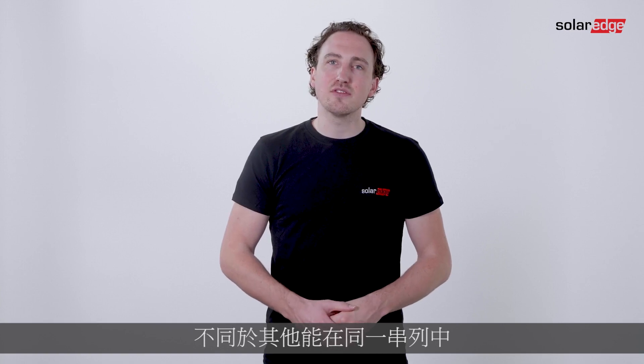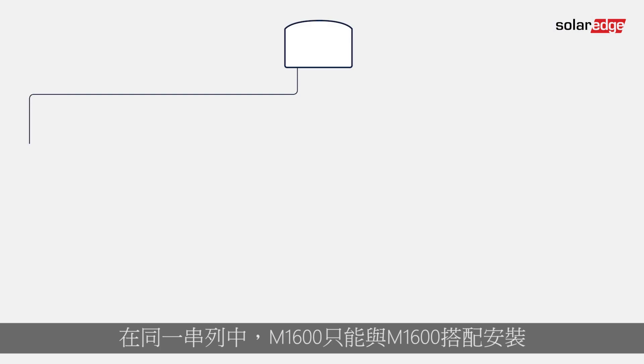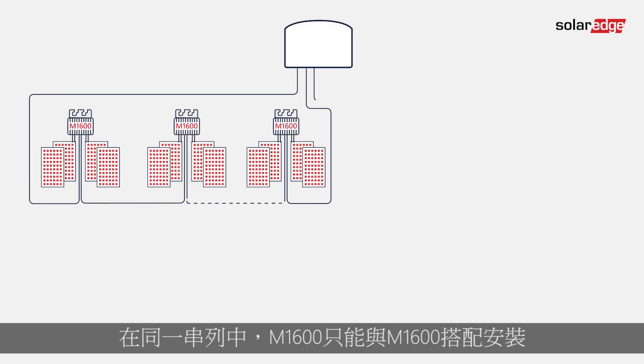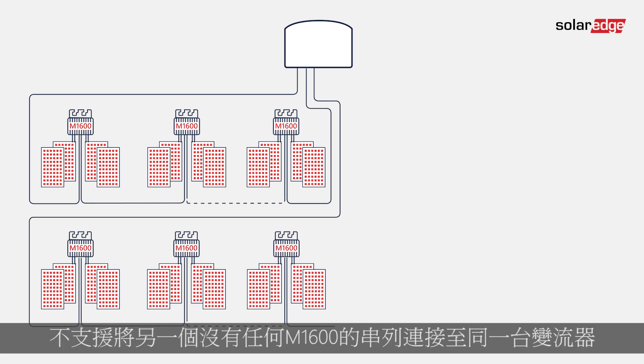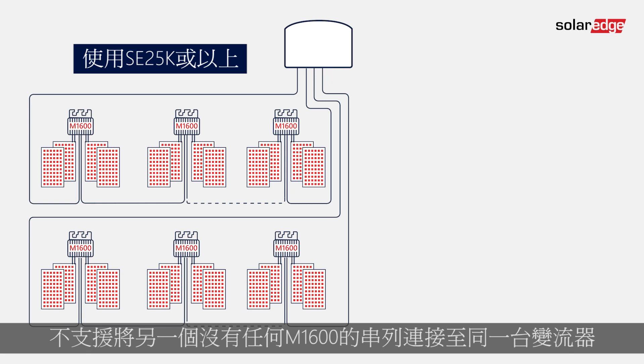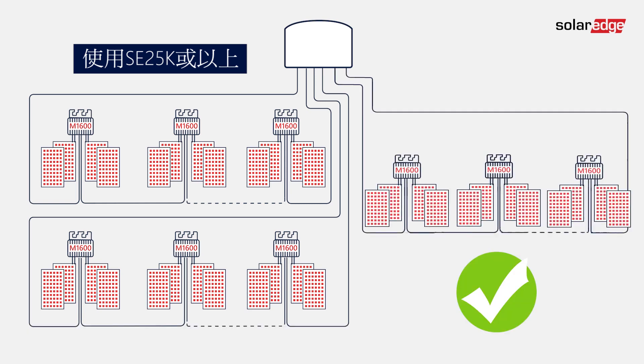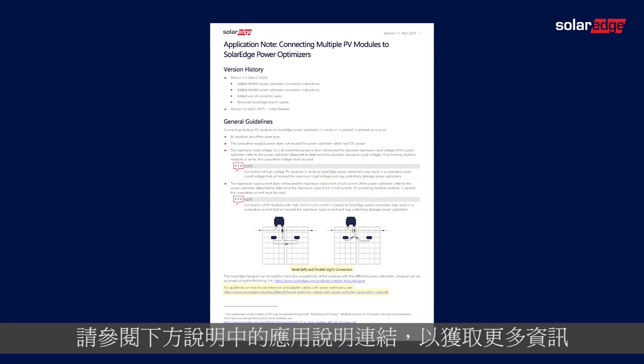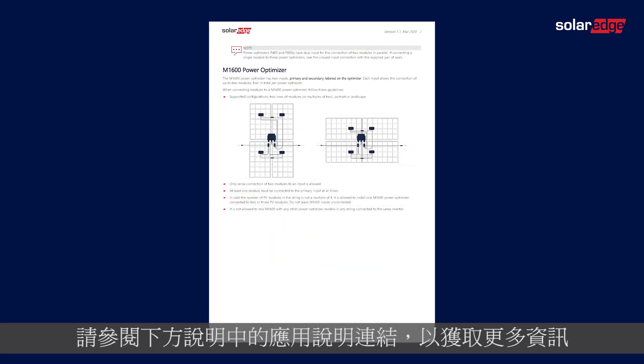Unlike other SolarEdge commercial power optimizers which can be mixed and matched on the same string, the M1600 can only be installed with other M1600 units in the same string. It is not supported to connect another string which doesn't include any M1600s to the same inverter. Find more information in the application note linked in the description below.